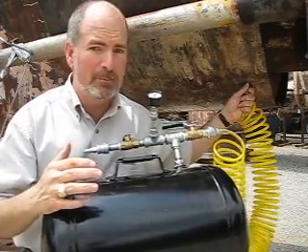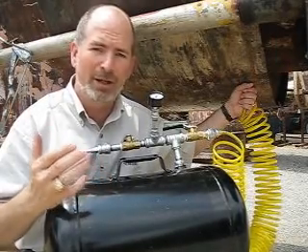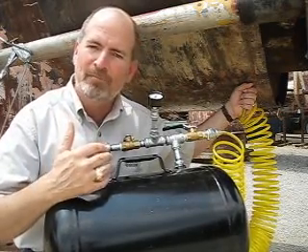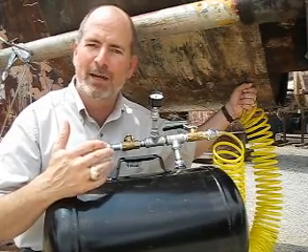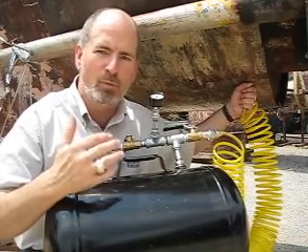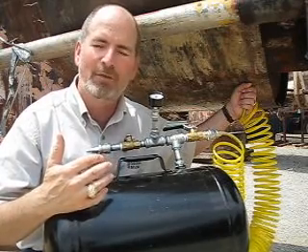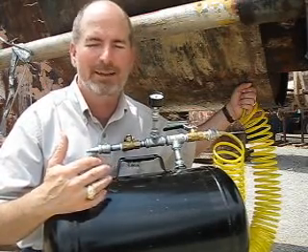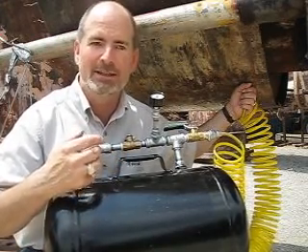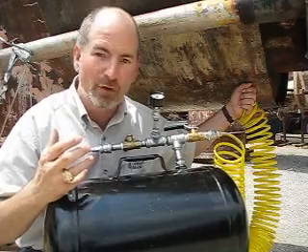And if you were to send your maintenance guys in there, and they were to hook up shop air right to that tap and put full pressure, 100 psi, that would collapse the inner ply. You don't want to do that. And even if you were to stick a regulator on there and regulate it down to 15 or 20 psi, what they would find is they would, with their valves, take a little bit of pressure in there and then shut it off, and they'd watch that pressure gauge, and then they notice a dramatic drop in pressure, and that might be a false indication of a failure of the inner ply. What is actually happening is the walls on the inside of those bellows are relaxing, and so the volume increases suddenly, and you've got such a small volume in there to begin with that it gives a false reading.